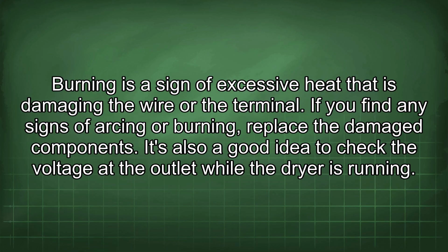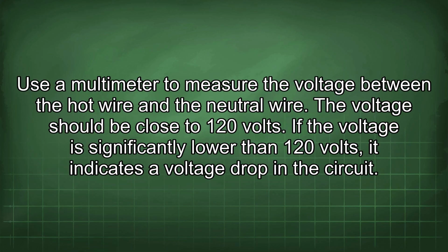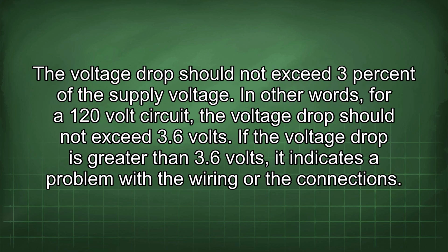It's also a good idea to check the voltage at the outlet while the dryer is running. Use a multimeter to measure the voltage between the hot wire and the neutral wire. The voltage should be close to 120 volts. If the voltage is significantly lower than 120 volts, it indicates a voltage drop in the circuit. The voltage drop should not exceed 3% of the supply voltage. In other words, for a 120-volt circuit, the voltage drop should not exceed 3.6 volts. If the voltage drop is greater than 3.6 volts, it indicates a problem with the wiring or the connections.